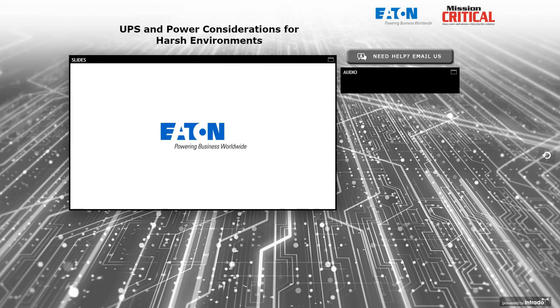When we say high capacity for a rectifier, for example, a rectifier usually handles the job of charging the batteries. So the client says, I've got a very large battery and I need it to be recharged very quickly. So that may mean that that rectifier is designed to direct more energy to the battery recharge circuit while still supporting the inverter. And technically that means the rating of the whole box goes up. So that's usually the reason for a high capacity rectifier.